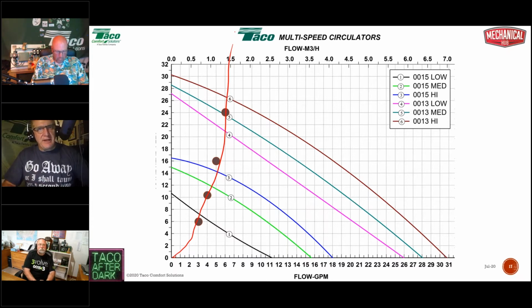Now, if I was a smart guy looking at this, and I've got a 3-speed circulator here, the Taco 0015 standard efficiency, 3 gallons a minute at 6 feet of head. If I'm a smart guy, I'm thinking, wow, 30,000 BTUs, 6 feet of head is kind of a lot if it's like a fin tube baseboard kind of thing. I'm looking at low speed here, man, speed 1, and that's going to be a really well-sized circulator.